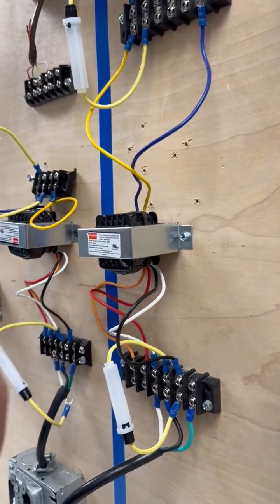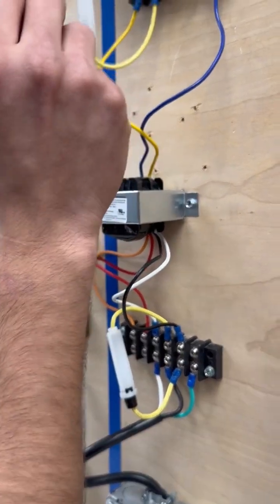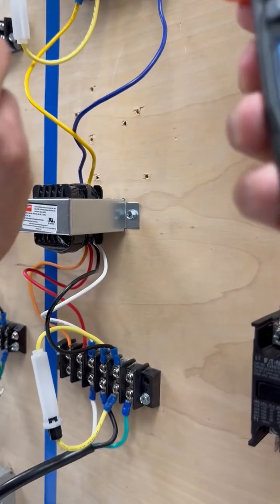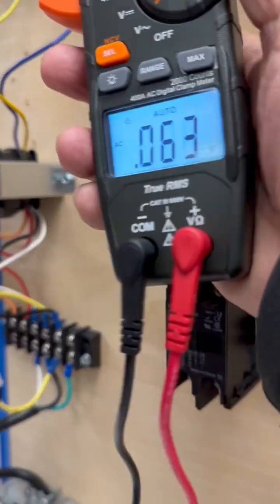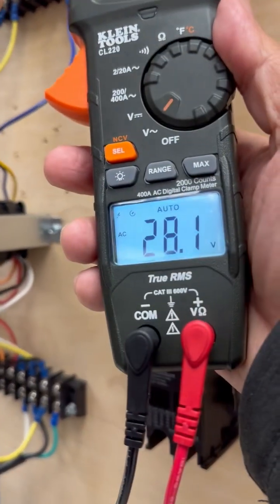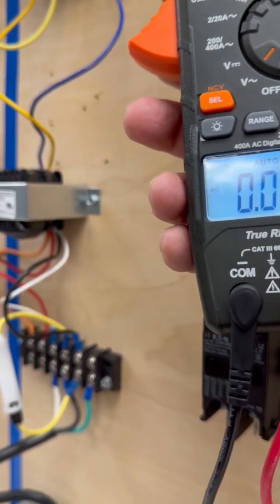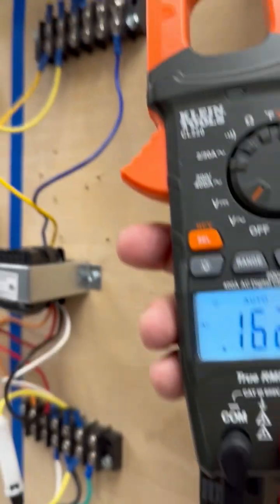Now on the secondary side, similar concept. We need a fuse holder for one of the hot legs. So here is our fuse holder. So we're expected to have 24 to 28 volts from both hot legs here. There's our 28 volts. Now we need 24 to 28 volts to supply to our thermostat.